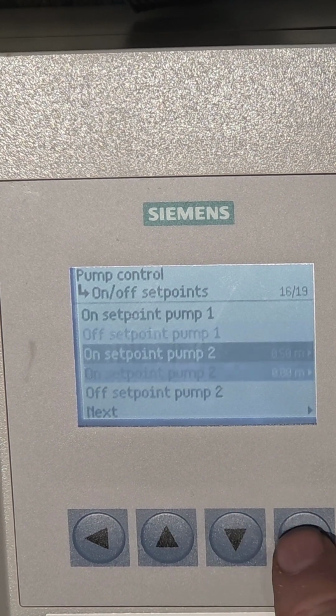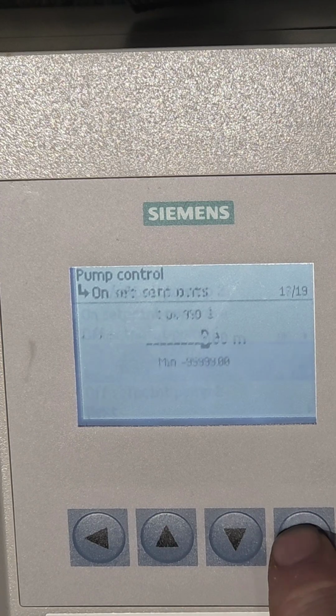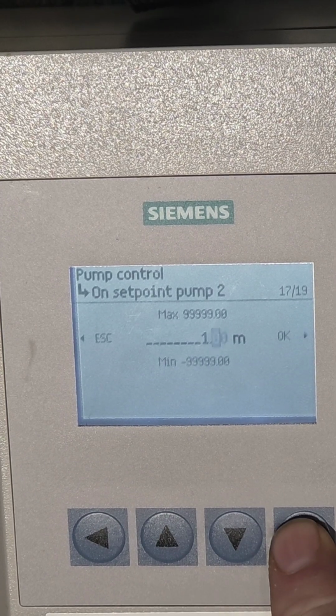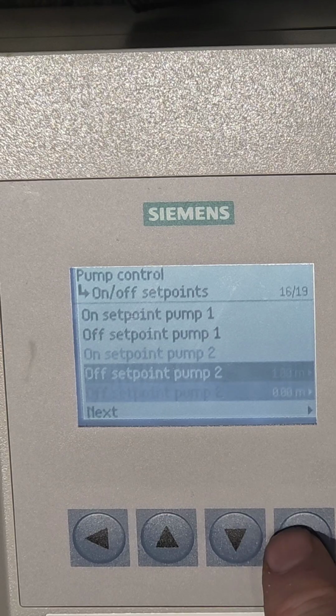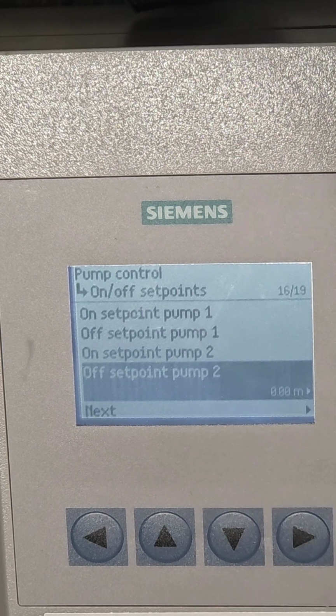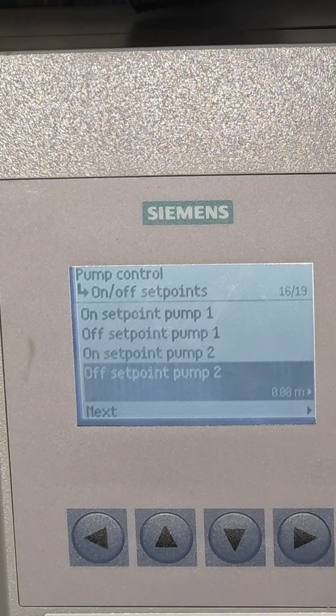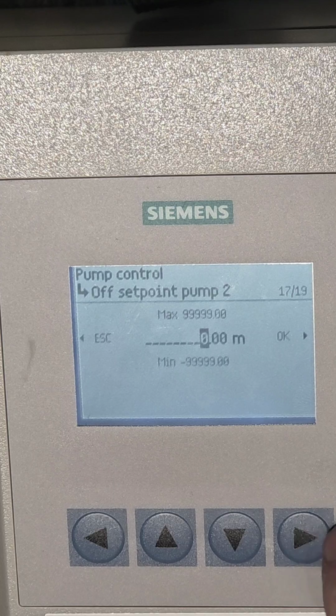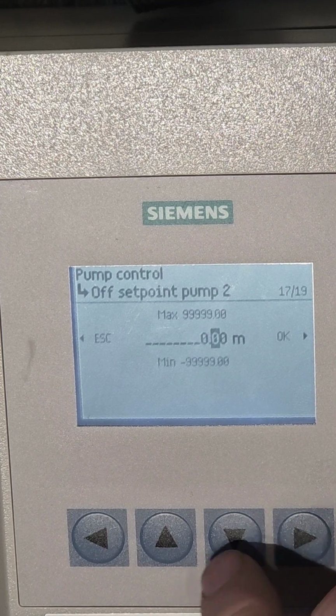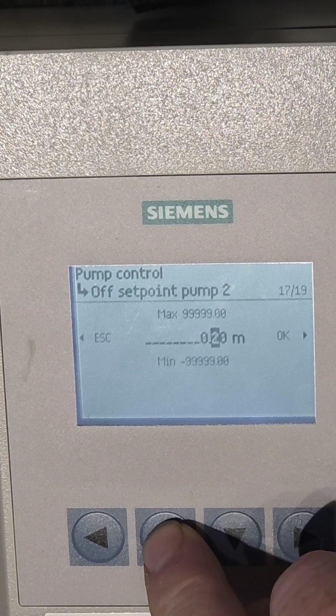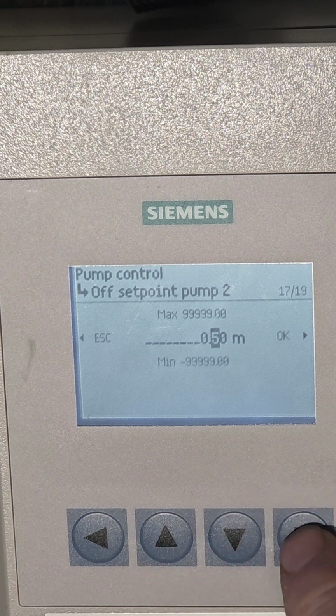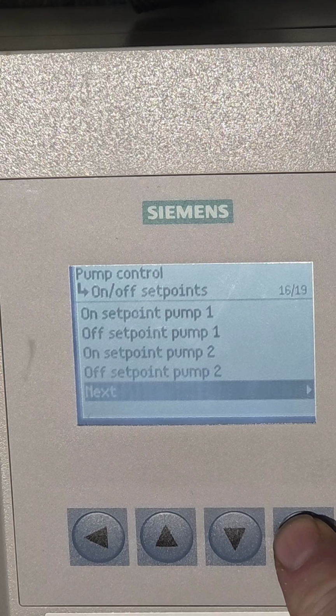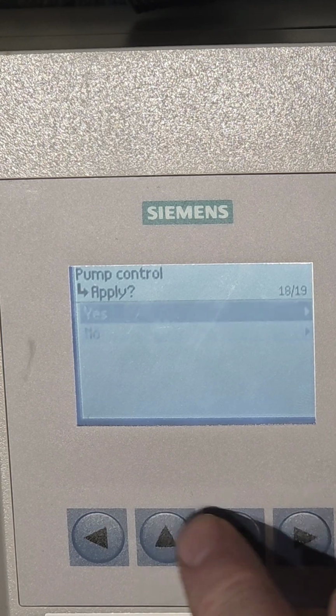OK. The on setpoint for pump number 2 is 1 meter. OK. And off is 0.5 meters as well. Pump 2, 0.5 meters, stop. OK. Down to next. Apply, yes.